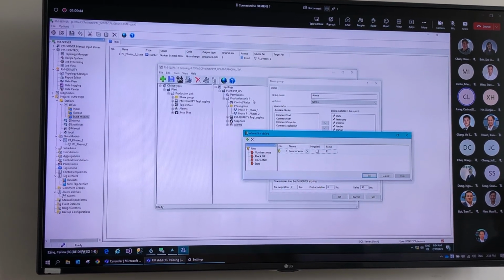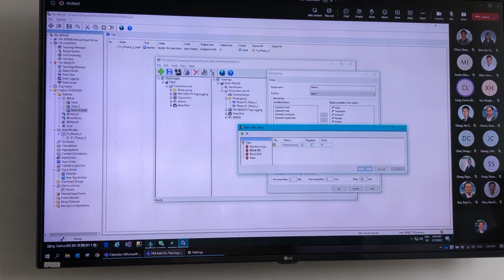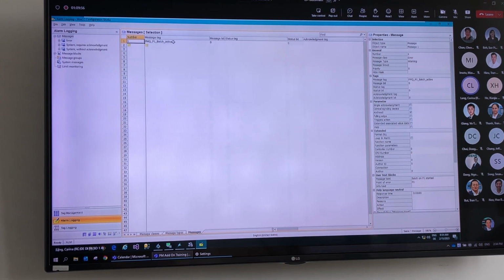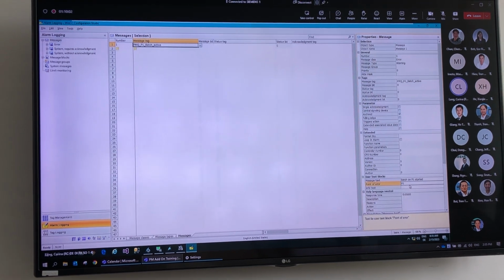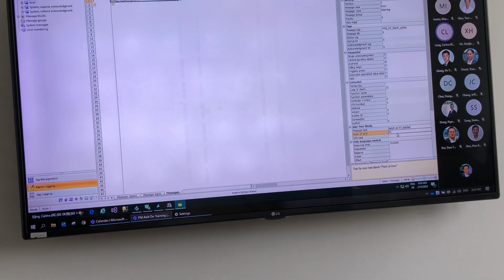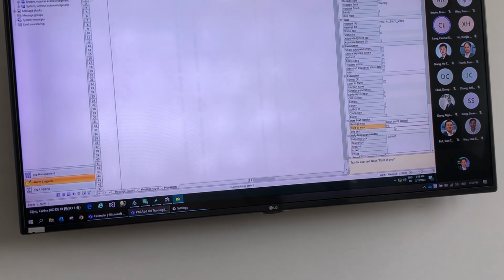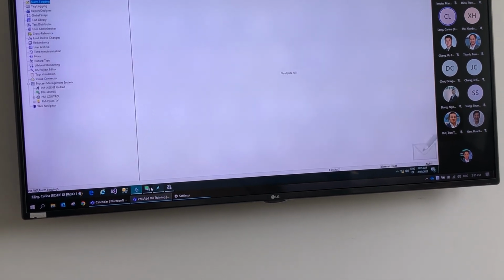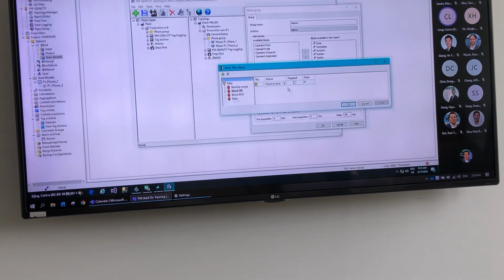This will work in my project here, because if we go back to my WinCC project and go to the alarm logging, then we will see that for this alarm I have configured, I have added the point of error P1. So of course, if you want to do something like that, be sure that you have the information inside of the alarm. If you do not have the information inside of the point of error, then you cannot filter using the point of error, because there's no data inside of it. So remember that.